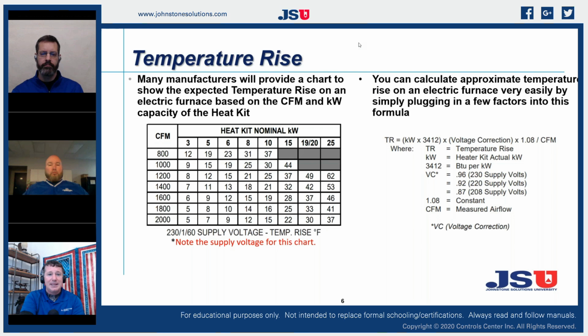So if we look at this heat kit nominal chart, that is giving us approximately those numbers. And it's a pretty good chart to have. Most electric furnaces have some type of a chart in them. And I've noticed a lot of the Goodman and Amana and some of the Daikins actually have charts for a variety of voltages as well. So they'll have one based at 230, one based at 240, one based at 208. And that gives us an opportunity to see what those correction factors are based on the voltage.